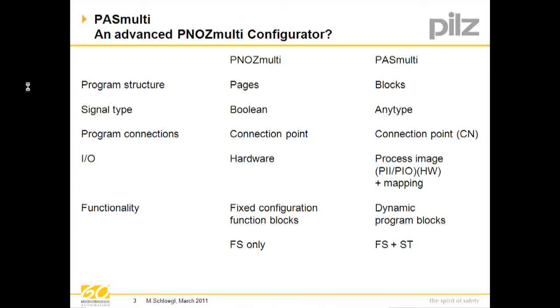Looking at the PASmulti, we have a hierarchical structure made up of blocks, and those blocks are nested in multiple layers to set up an application. Looking at the signal type, within the PNOZmulti there are only Boolean signals, whereas within PASmulti, as with any editor within the PSS 4000 system, we named it any type, so any variable type supported by the system can be used in the PASmulti editor.